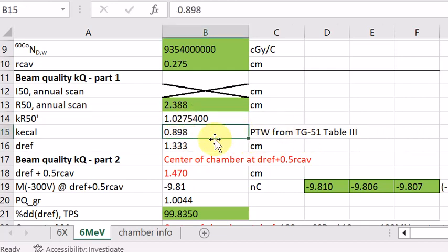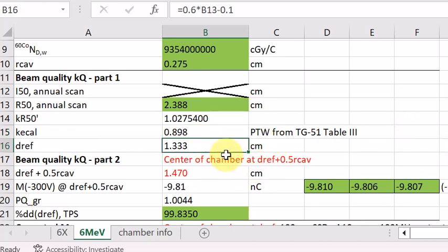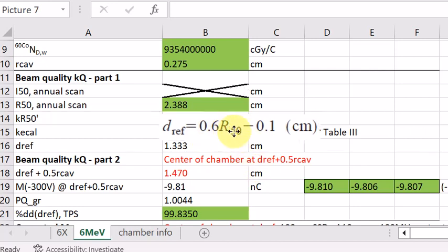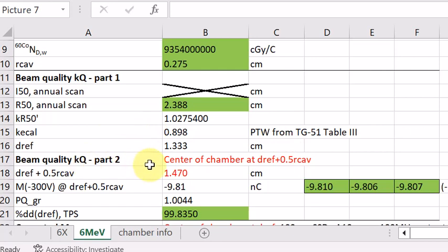The KECAL factor is obtained from the chamber type using Table 3 in TG51. The reference depth DREF is also very important — it is where the center of the chamber is placed for the actual measurement. This DREF is closely related to the R50, and is also calculated from the TG51 scan using its corresponding equation.